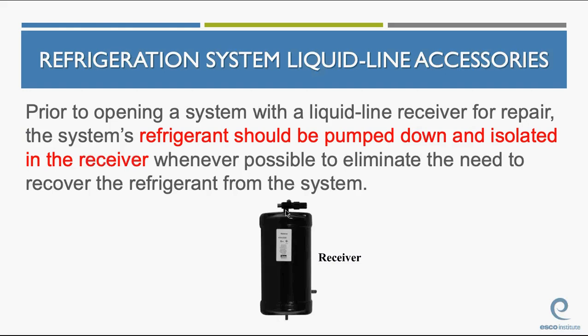Prior to opening a system with a liquid line receiver for repair, the refrigerant should be pumped down and isolated in the receiver whenever possible. I can close the valve on the receiver, and I can actually isolate the refrigerant into the receiver. Most receivers are sized so that you can fit the entire charge of the system into the receiver and the condenser.